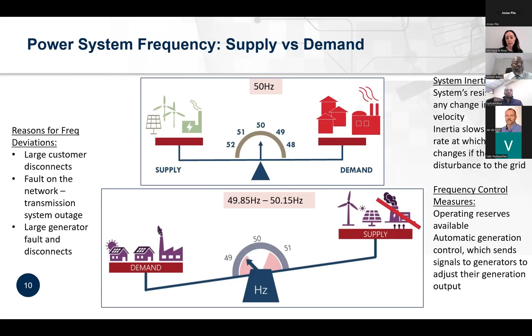And that brings us to system inertia and what that is. System inertia is the system's resistance to change in the velocities. We know that the big coal-fired power stations or the big hydro stations have big rotating masses, big machines that spin around, and there's an inherent energy caught up in those rotating machines that will cause the system to be resistant to change. So if there's a small change on the system, it can easily ride through that, and that keeps our system very stable. Traditionally, South Africa has had a very stable system due to this, because we've had large generators all connected to the grid that keep our system stable. But in future, that might change a little bit as some of that traditional baseload power gets replaced by renewable energy generators, which are small machines that don't keep the grid as stable and bring other considerations into play.